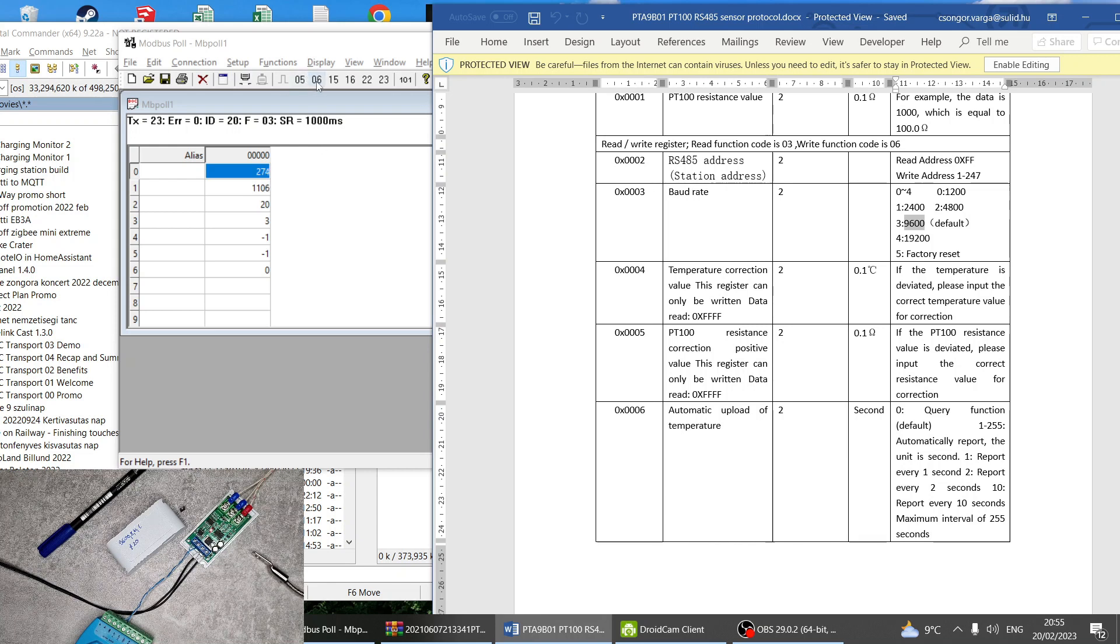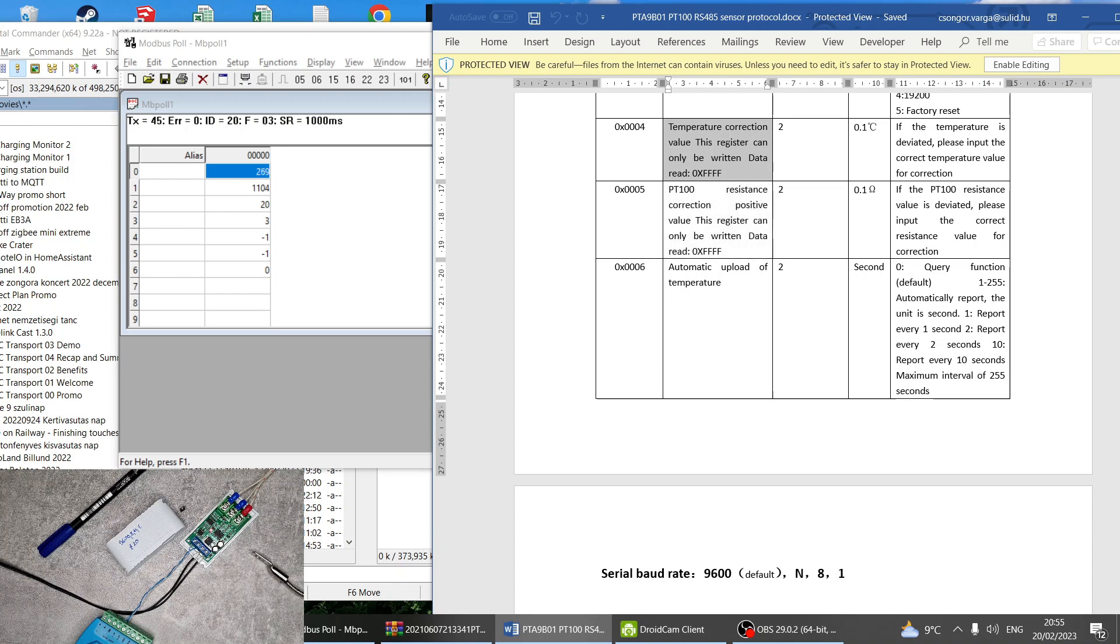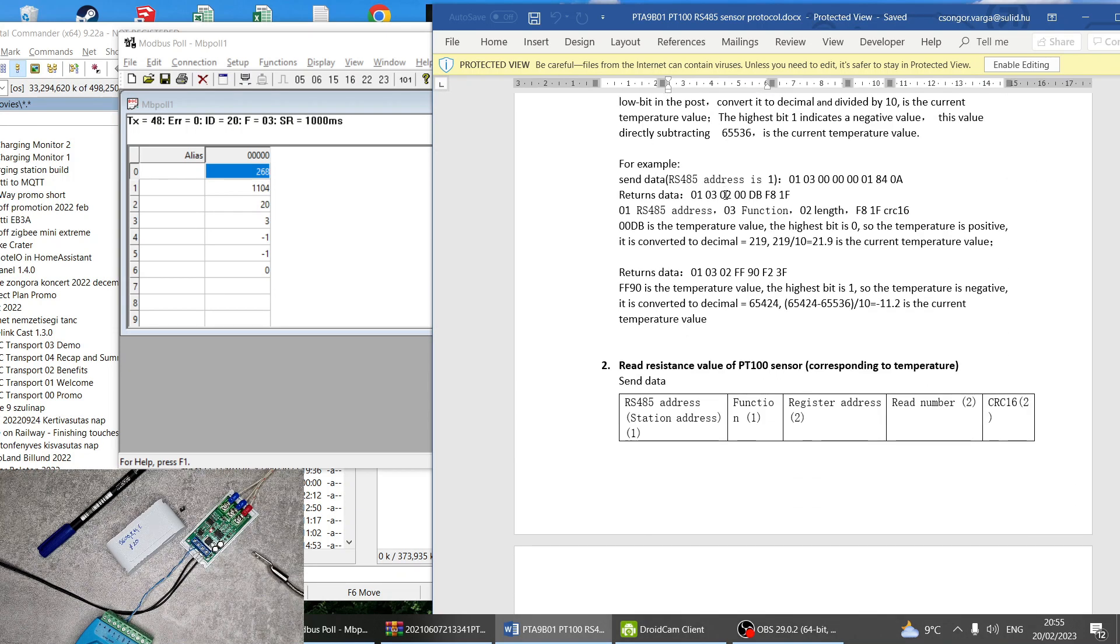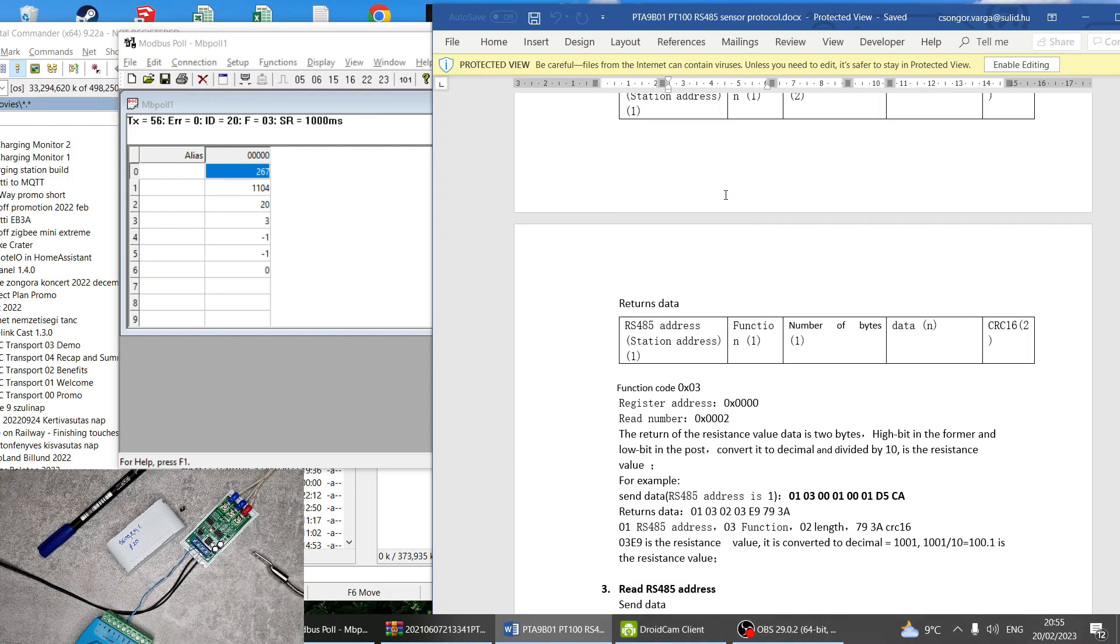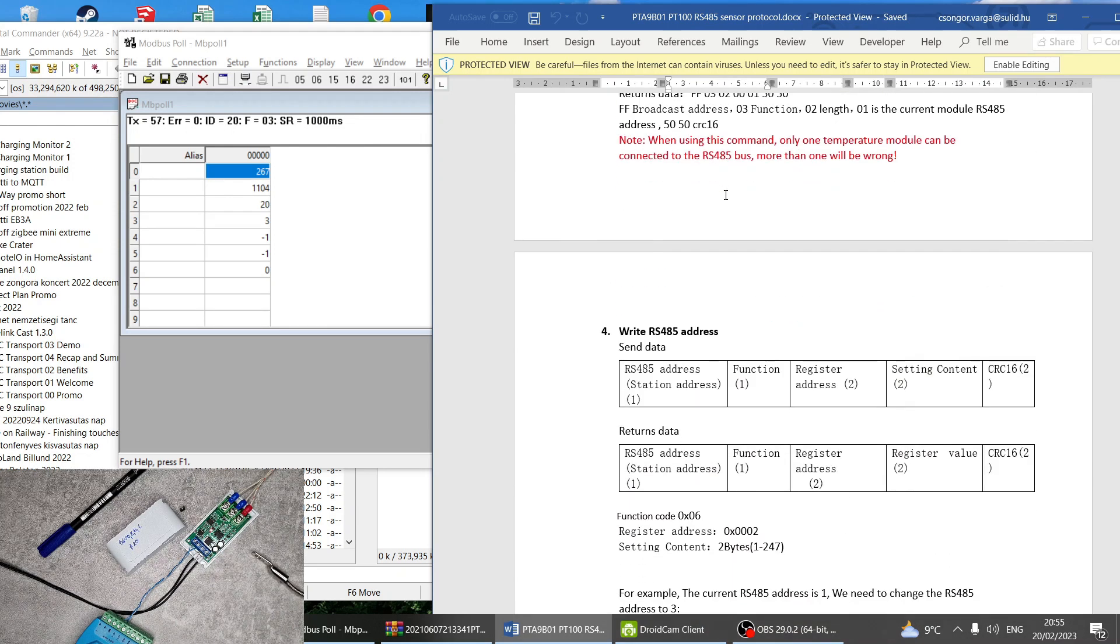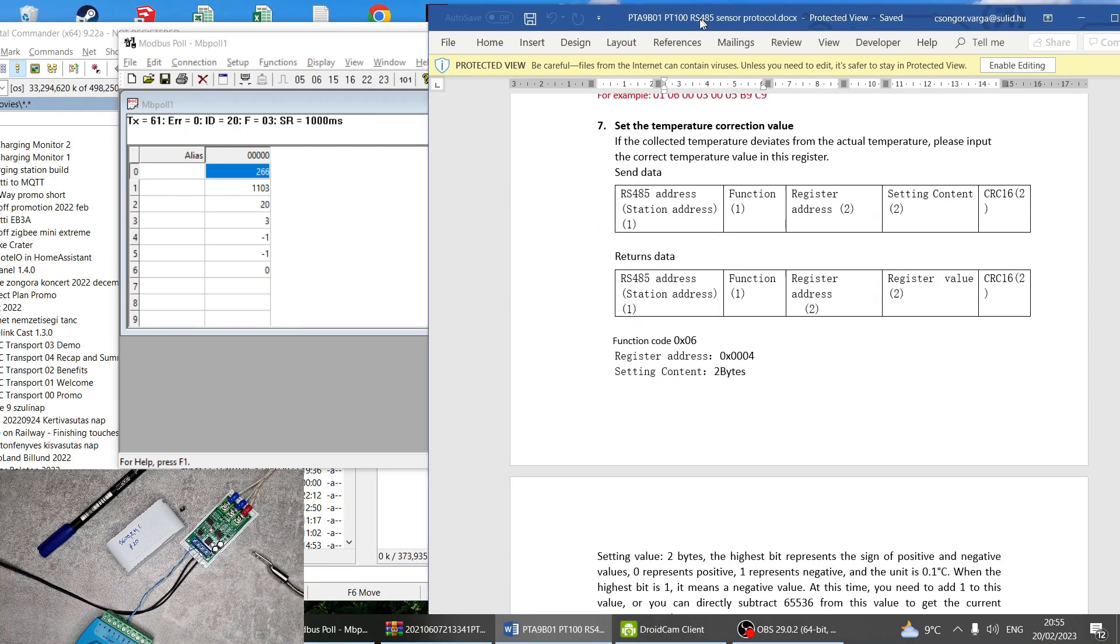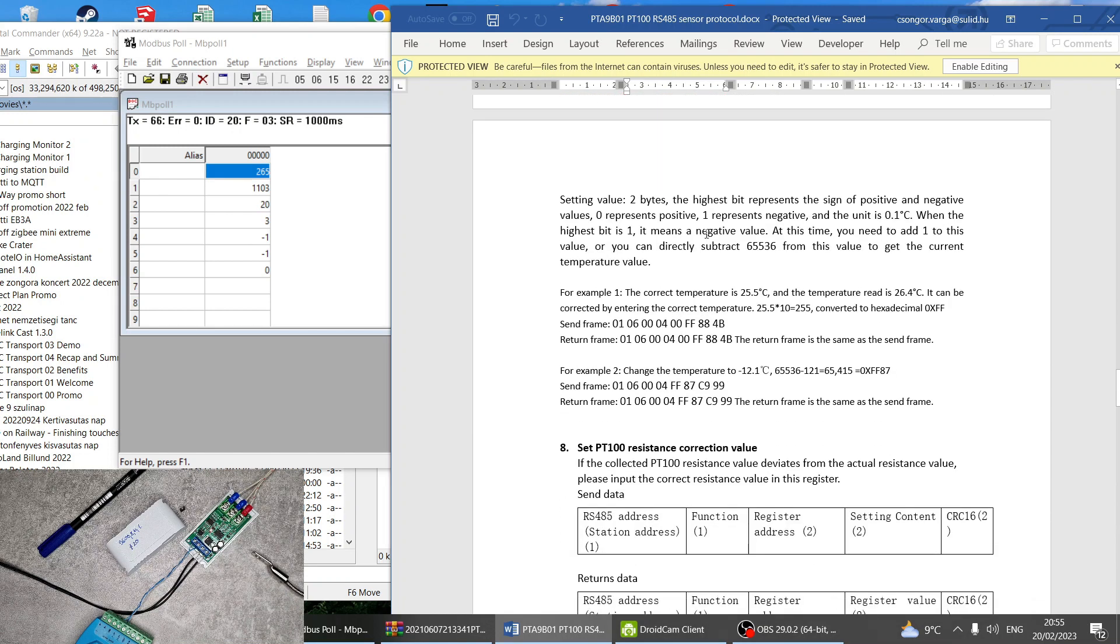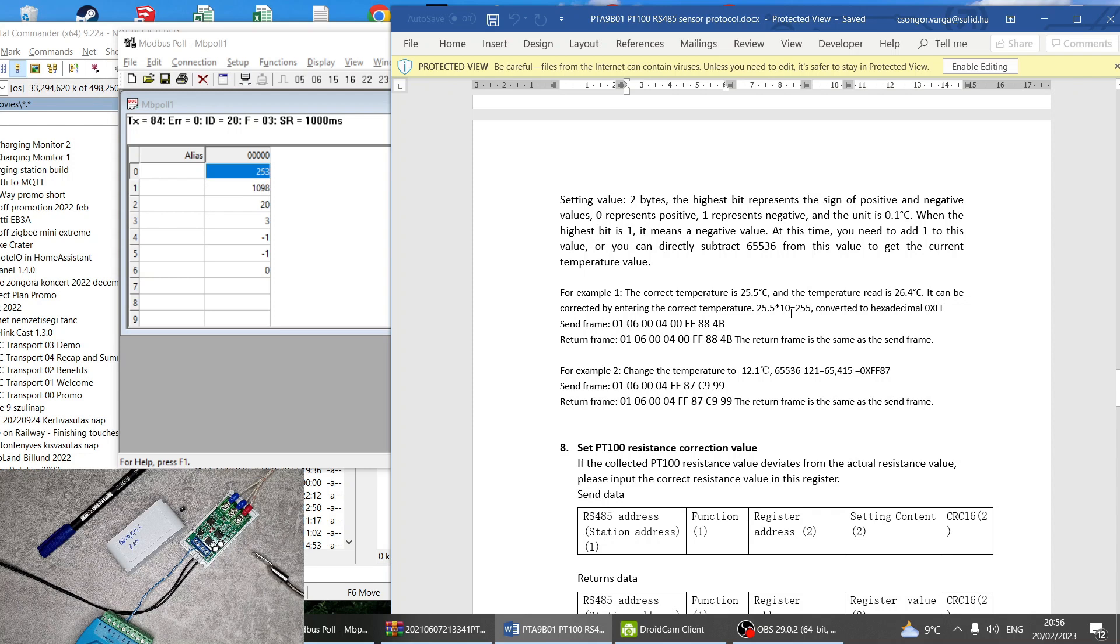There is one quirk with the temperature and the resistance correction. Instead of sending a like a +1 or -1 of how much to correct, what you send is the data that you want the device to read. So for example, it shows you an example: if the device measures 25.5, so if you know that the correct temperature is 25.5 degrees but then the temperature which is read is 26.4, so instead of sending 0.9 as a correction you actually send the value that you want to be measured.